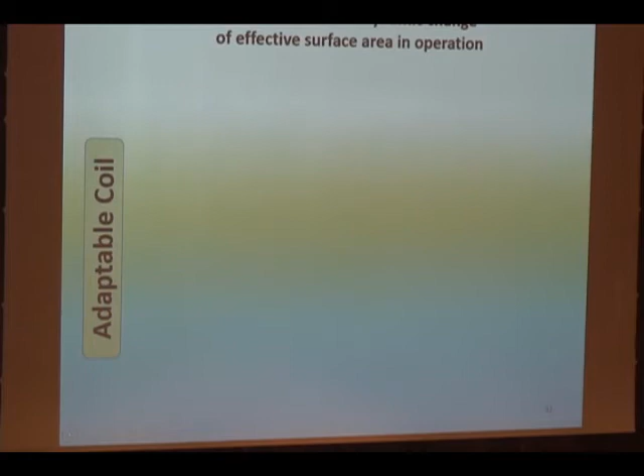A large cooling coil being able to reduce in terms of its effective surface area in operation. This is a consultant's design for a 200 kilowatts capacity, the large cooling coil. We have airflow from bottom to up on the screen. The chilled water flow goes through row 6. It comes out at row 4. We collect it in the manifold. There's a little bit of a manipulation that we do here. The water can go back to row 3 and comes out at 1.